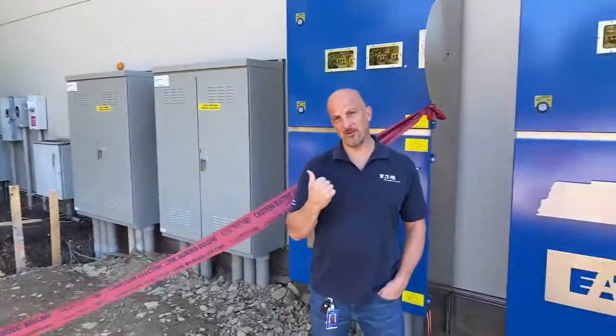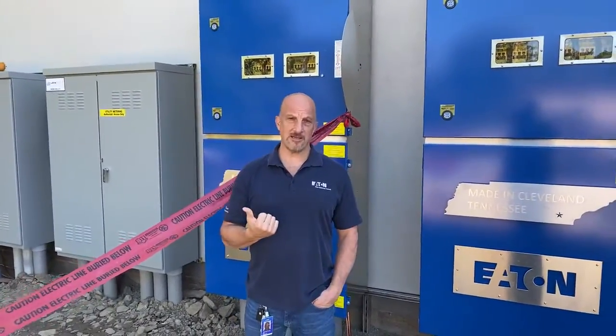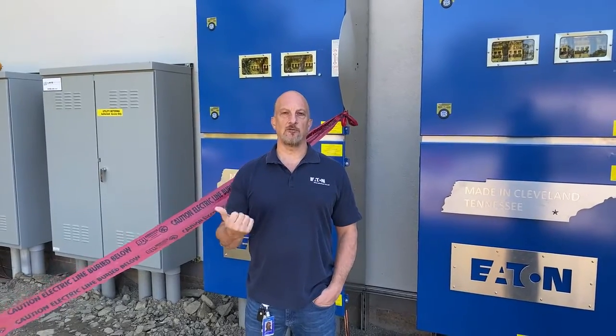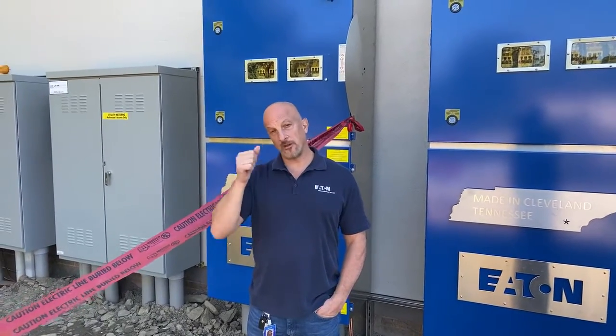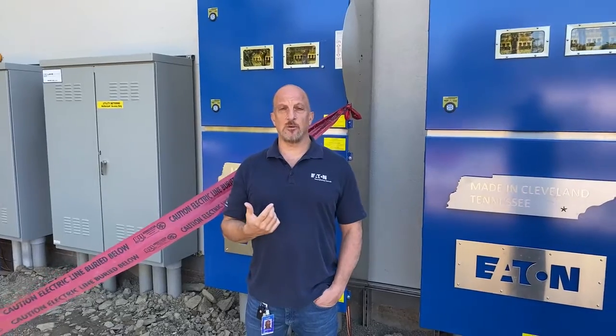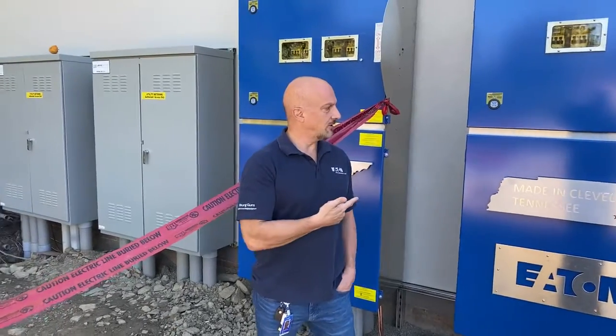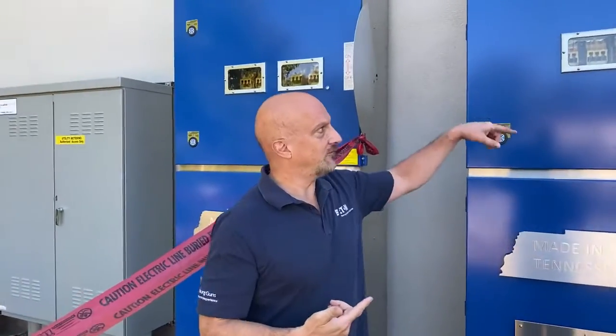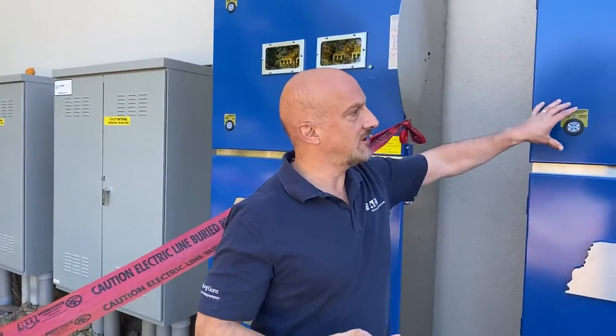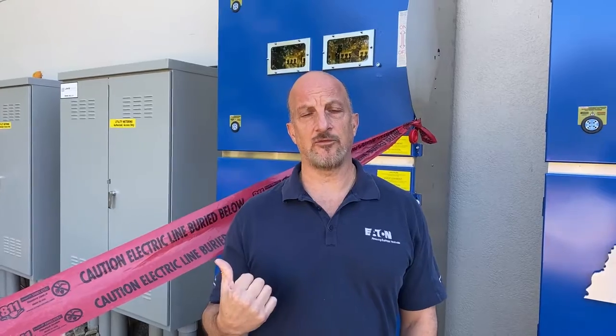Because inside the building, as in many cases, the arc flash levels are above 40 calories just on the other side of the transformer. So in this case, what we wanted to do was put in two new double door safety switches, by the way, so we could have isolation, and then bring the power into there so we could do our own shutdowns from out here.